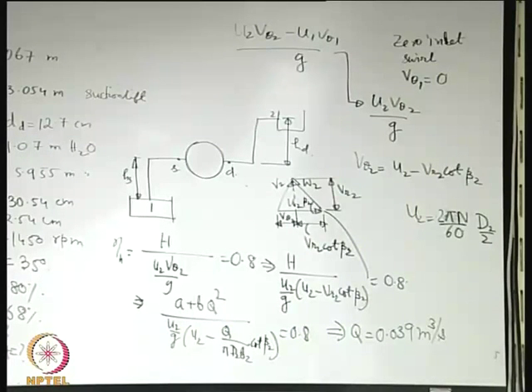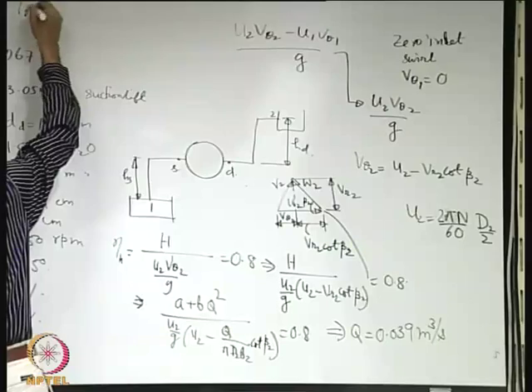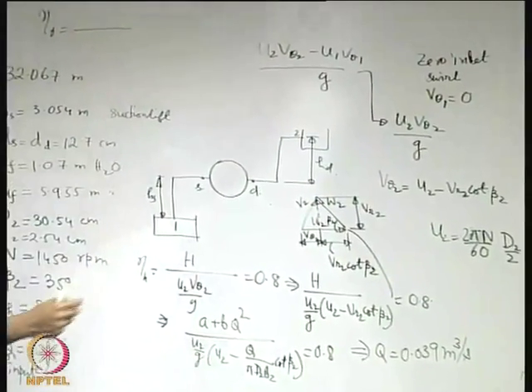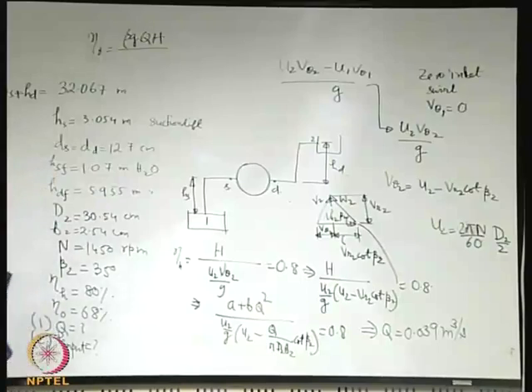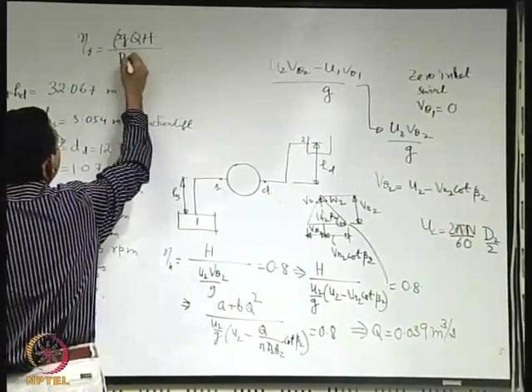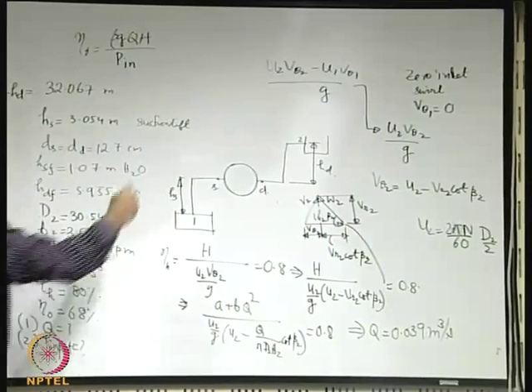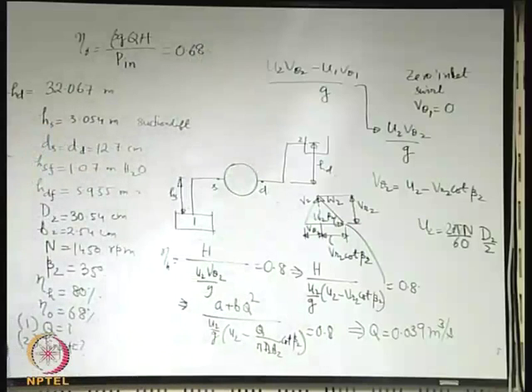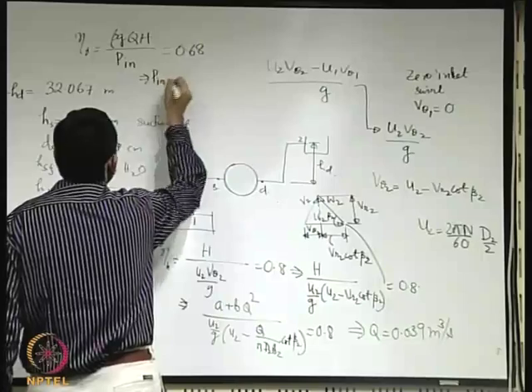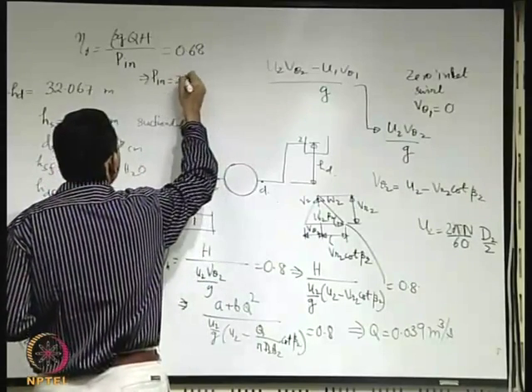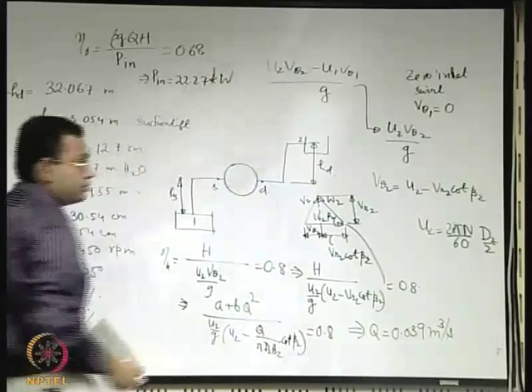For the second part, the power input is related to power output by the overall efficiency. The power output is ρgQH, and the overall efficiency is 68%. Dividing power output by 0.68 gives the power input as 22.27 kilowatt.